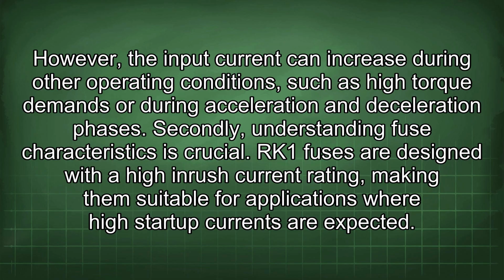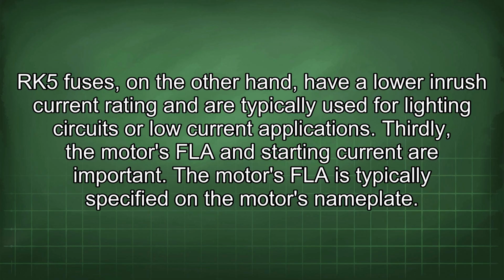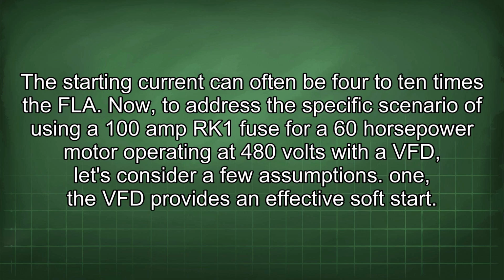RK1 fuses are designed with a high inrush current rating, making them suitable for applications where high startup currents are expected. RK5 fuses, on the other hand, have a lower inrush current rating and are typically used for lighting circuits or low current applications. Thirdly, the motor's FLA and starting current are important. The motor's FLA is typically specified in the motor's nameplate. The starting current can often be 4 to 10 times the FLA.